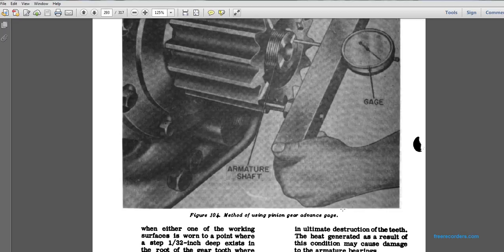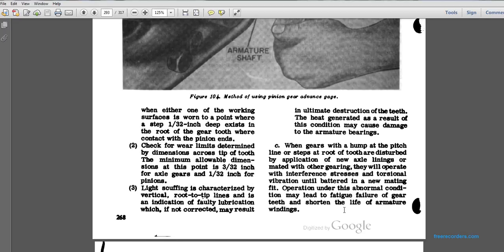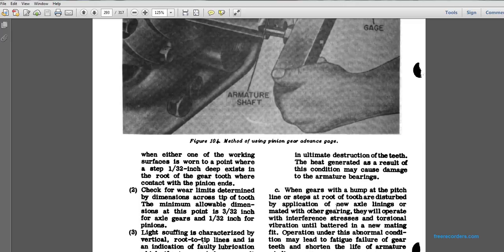Visual inspection: pinion and axle gears should be condemned when more than 20% of the total working surface of the teeth are spalled and pitted, or axle gears should be scrapped. This shows you the gauging of the pinion gears and the axle gears with the armature shaft gauge. When either one of the working surfaces is worn to the point where a depth of 1/32 of an inch exists in the root of the gear tooth, check the wear limits determined on the dimension across the tip of the tooth. The minimum allowable dimension is 3/32 of an inch for an axle gear and 1/32 of an inch for a pinion.